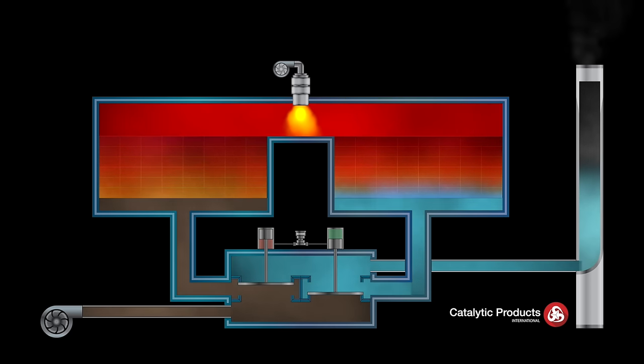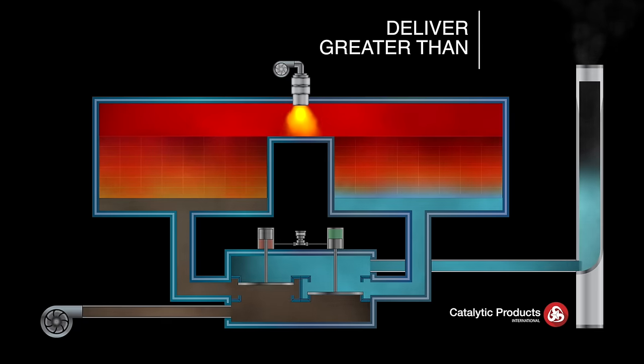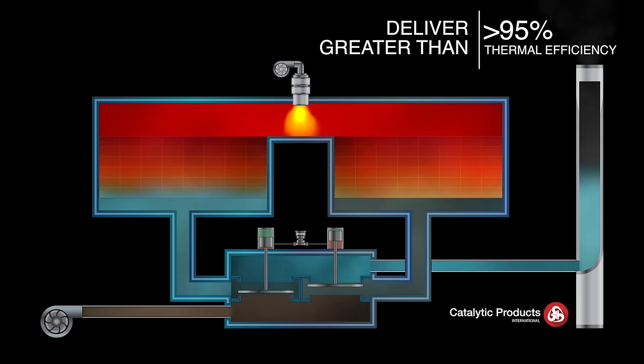It is this regeneration of the ceramic heat exchanger media with its high heat capacity which enables a regenerative thermal oxidizer to deliver greater than 95% thermal efficiency.